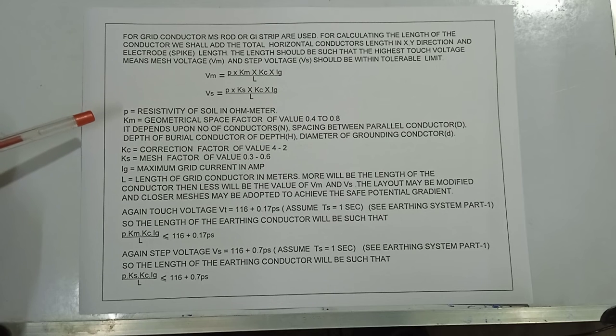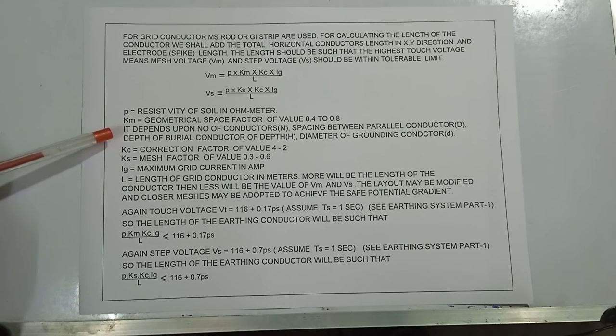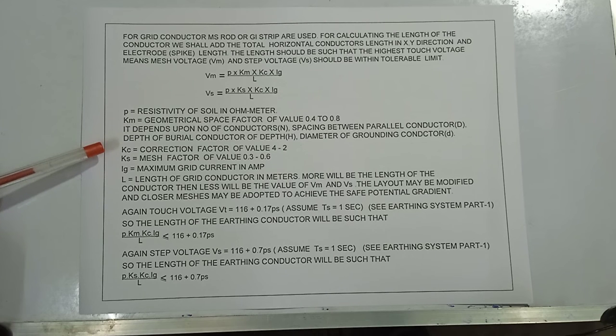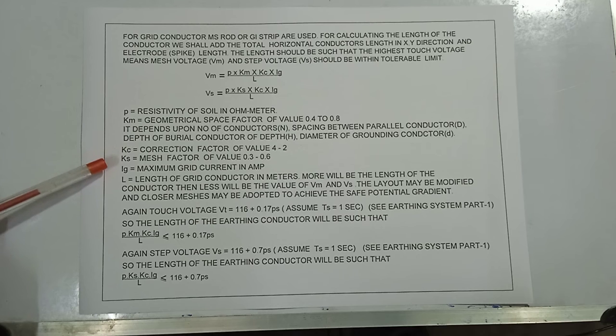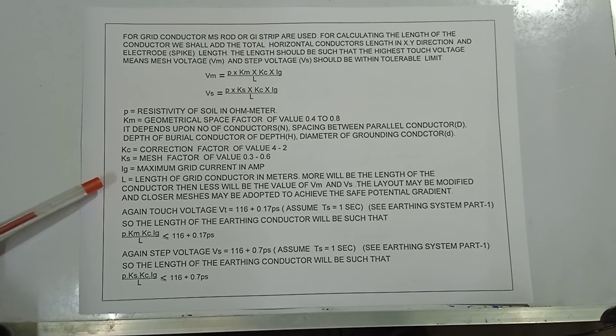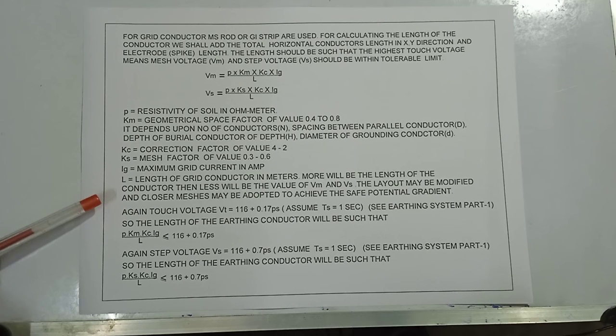Where: ρ is resistivity of soil in ohm-metre; Km is the geometrical spacing factor with value 0.4 to 0.8, depending on number of conductors N, spacing between parallel conductors D, depth of buried conductor H, and diameter of grounding conductors d; Kc is correction factor with value 4 to 2; Ks is mesh factor with value 0.3 to 0.6; Ig is maximum grid current in amperes; and L is total length of grid conductor in metres. A greater conductor length results in lower Vm and Vs values. The layout may be modified and closer meshes adopted to achieve the required potential.